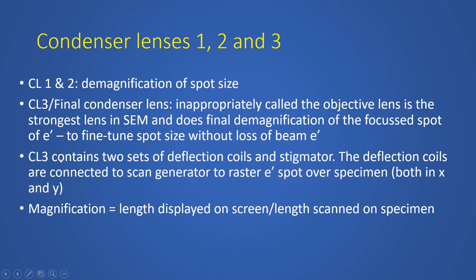The condenser lens 3 also has sets of deflection coils and stigmators. Stigmators are something that compensates for an aberration called astigmatism. Okay, we'll come to it later. So these deflection coils are connected to the scan generator. This helps in raster scanning the electron spot over the specimen.